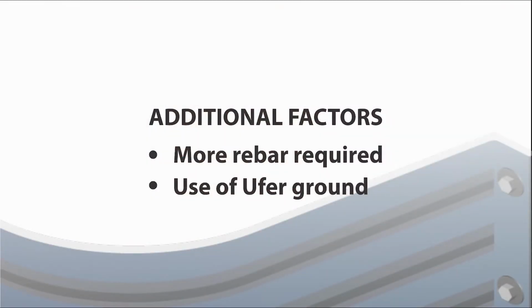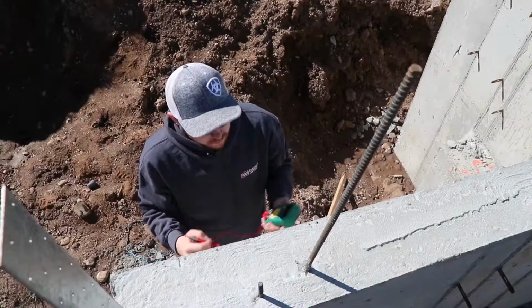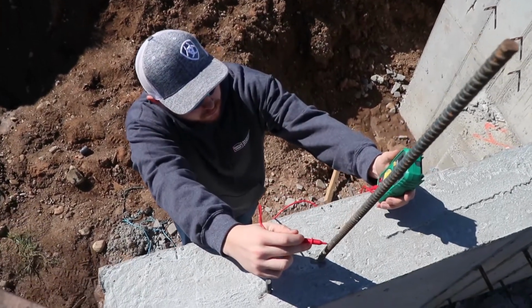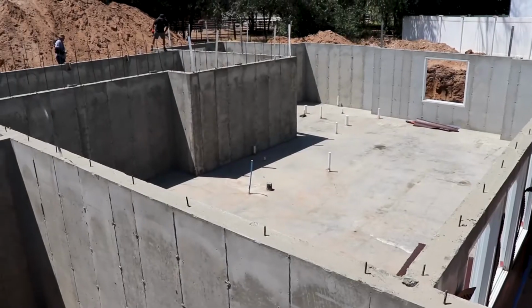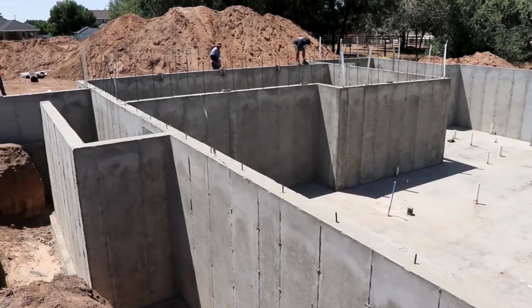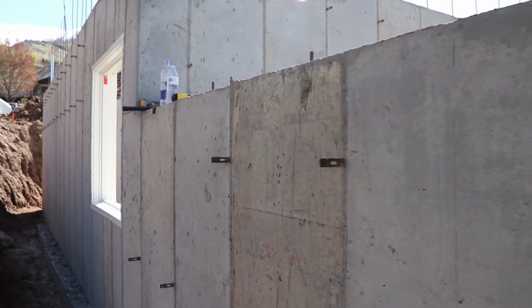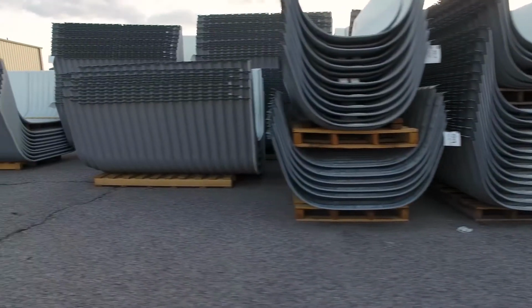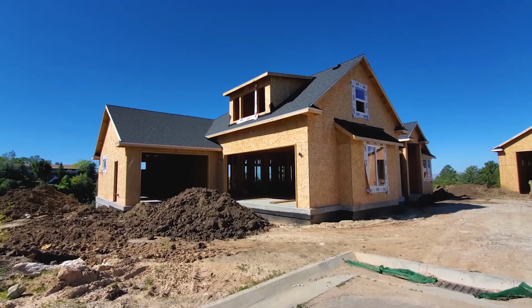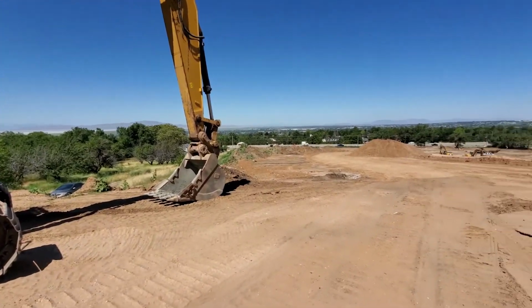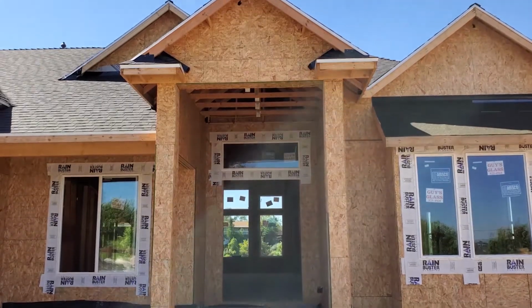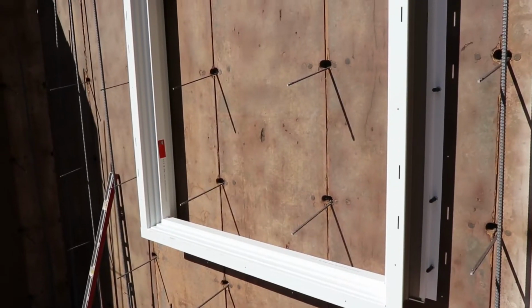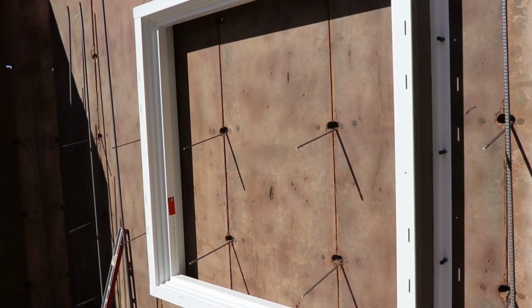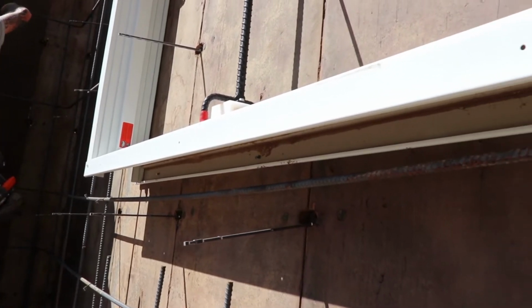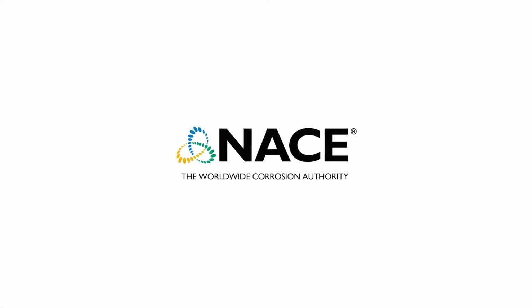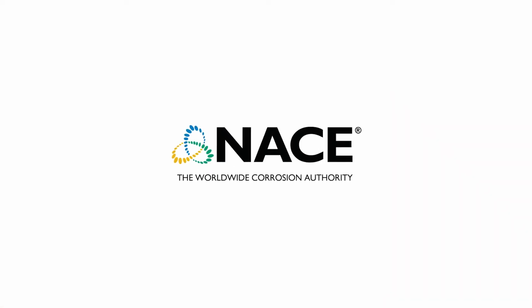Second, UFER ground. The introduction to the electrical code of the use of UFER ground, which grounds the electrical system to the rebar in the foundation. The UFER ground and network of rebar function as an electrical conductor. These changes in home building practices have an impact individually and together. Qualcore's research helped us to identify exactly what was causing the window wells to corrode. Their subsequent recommendations are based on standards set by the National Association of Corrosion Engineers.